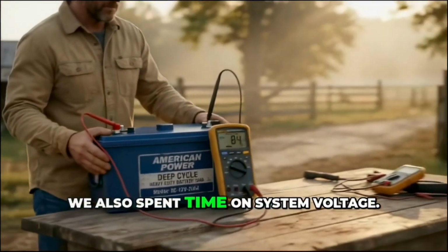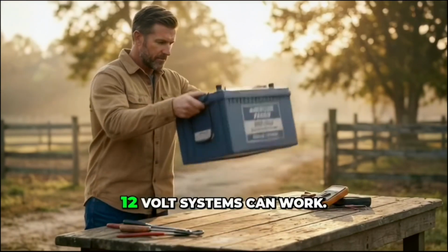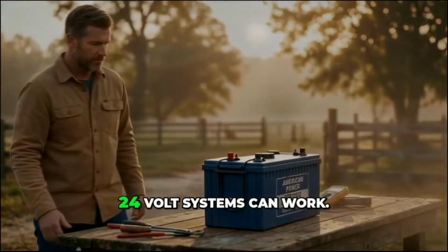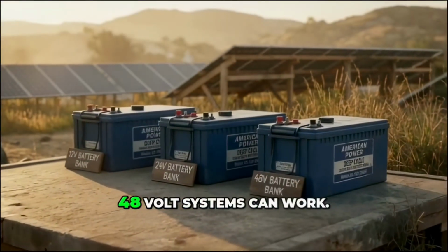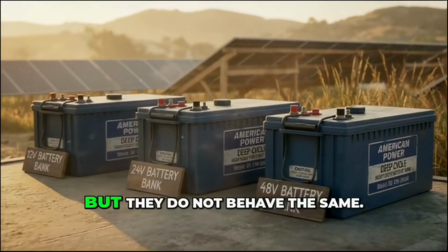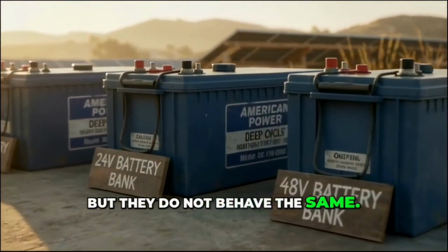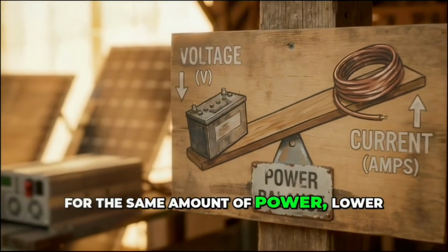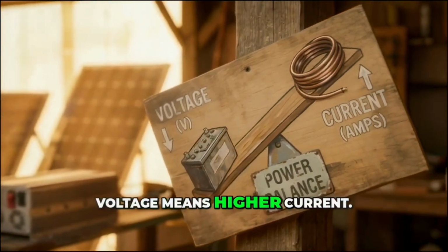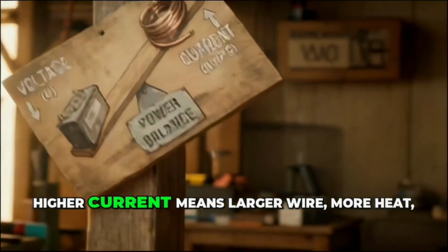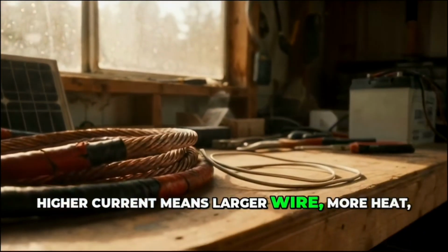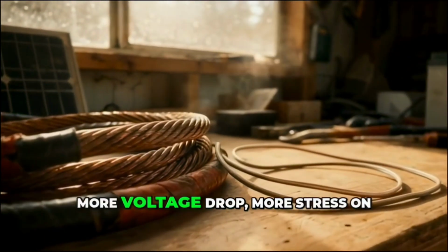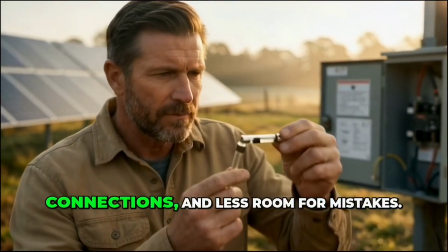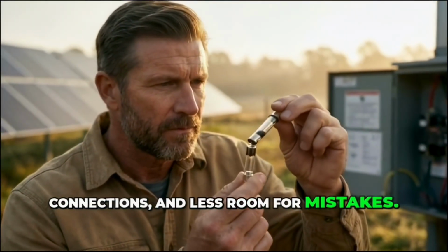We also spent time on system voltage. 12-volt systems can work. 24-volt systems can work. 48-volt systems can work. But they do not behave the same. For the same amount of power, lower voltage means higher current. Higher current means larger wire. More heat. More voltage drop, more stress on connections, and less room for mistakes.